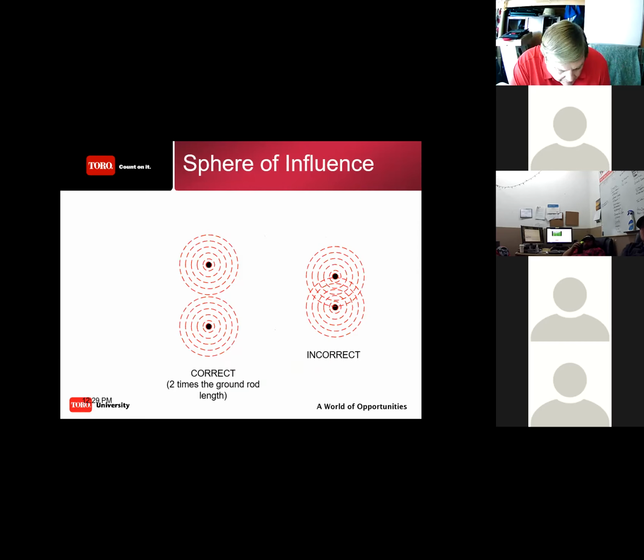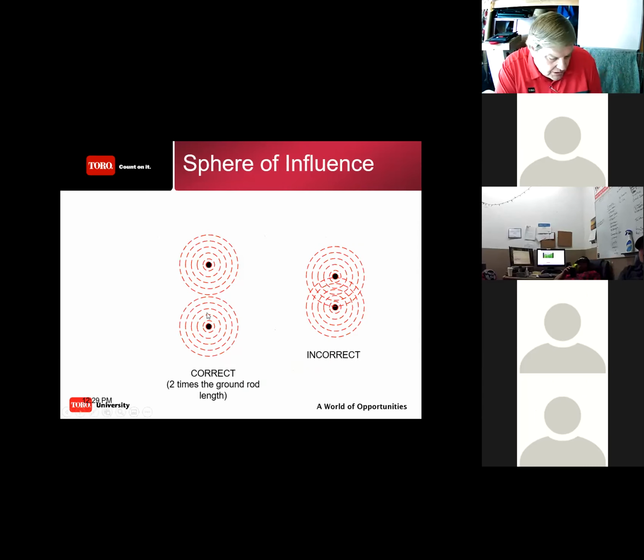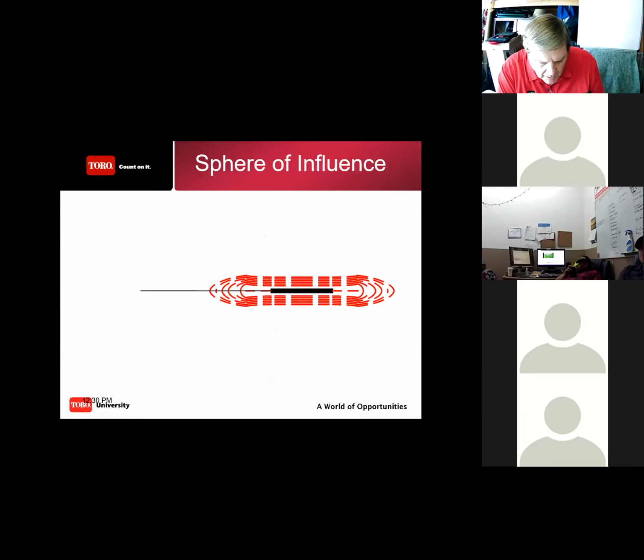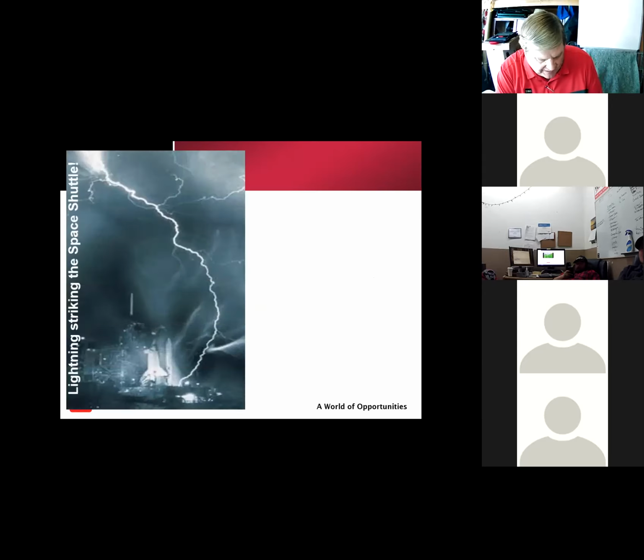If you put 2 ground rods in the ground for better protection, be aware of the distance between them. If you put them too close together, you're not going to have appropriate protection from that grounding setup. Ground sphere or ground plane, your sphere of influence is predominantly on the leading edge or away from it, not side by side. So it's just an example of, again, the sphere of influence on that one.